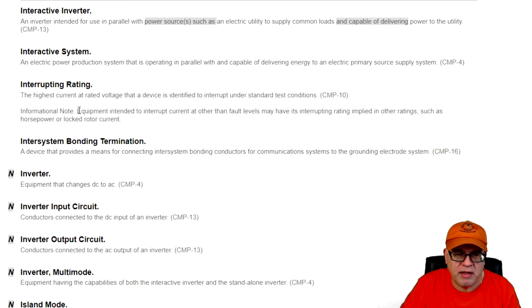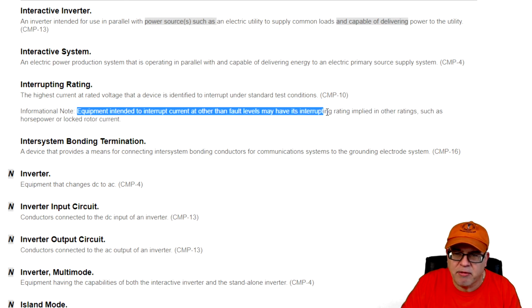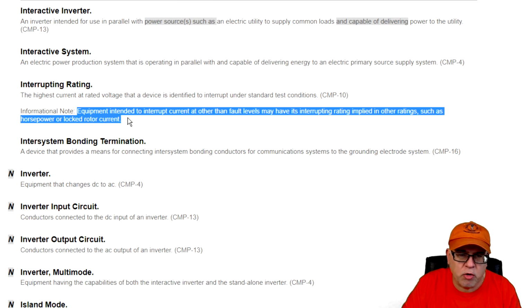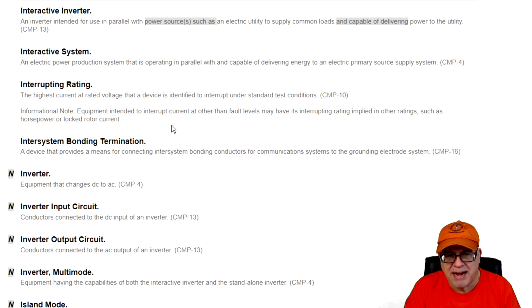An informational note says, for example, equipment intended to interrupt current at other than fault levels may have an interrupting rating implied in other ratings, such as horsepower or even locked rotor current. Okay, so you have other ratings that could give the interrupting current other than fault levels. So you could have something that's rated in horsepower. You could have something rated in locked rotor current. Most of the circuit breakers that we see, main breakers and panels, things like that, have an IR rating, and it's actually the current rating at the applied voltage, and that is the highest current that it can handle and work safely. So that's why we need to know what available current is, and that's how we have to know that.